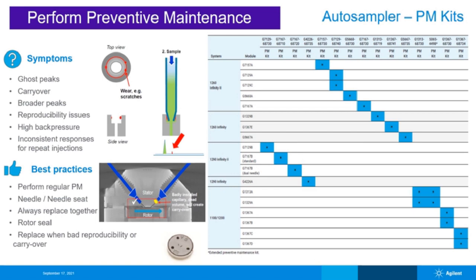Common sources of autosampler issues include the exterior of the needle, a worn needle seat, a worn rotor seal in the injection valve, or a poorly made fitting. To simplify your life and operate your autosampler at its best, I suggest you choose the right autosampler maintenance kit from the table below. Each of them includes the right maintenance parts for your specific autosampler model.